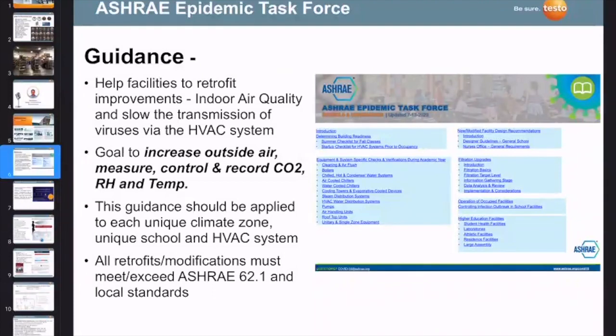One thing they realized, looking at a lot of the medical research, was that it was quite evident back in March, April, and May that this was not just contact transmittance, but also airborne transmittance. Hence the reason to optimize HVAC by increasing outside air and increasing outside airflow to the point that you're actually trying to mitigate and dilute the airflow down. A way to keep track of that is by looking at CO2, relative humidity, and temperature in classroom spaces or any occupied space in a school. This new guidance should be applied across all climate zones, across all districts nationwide.